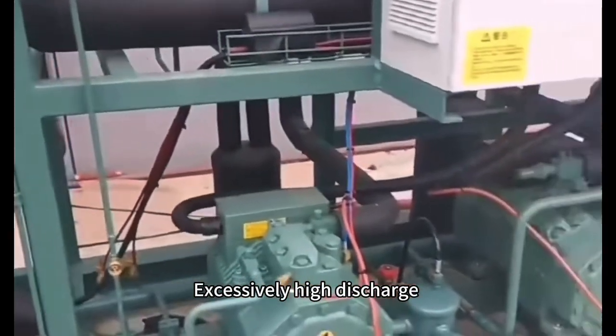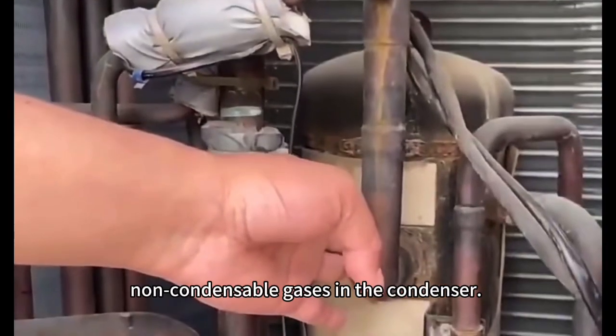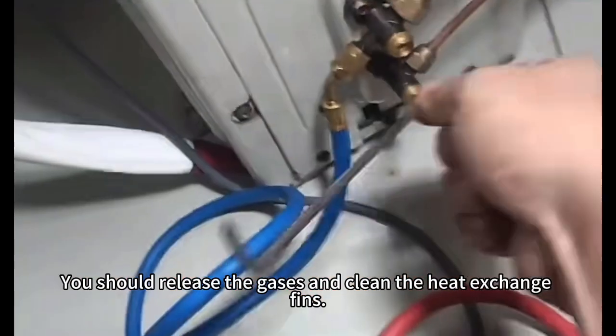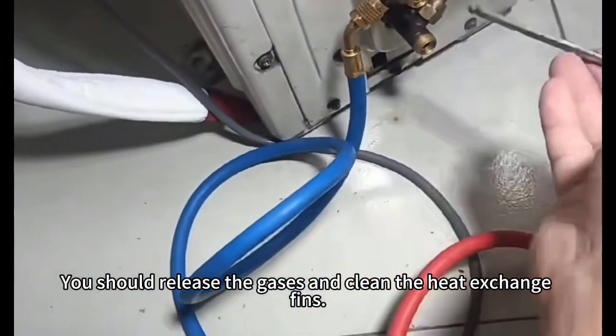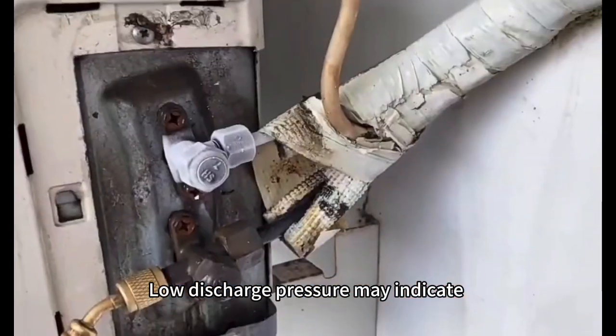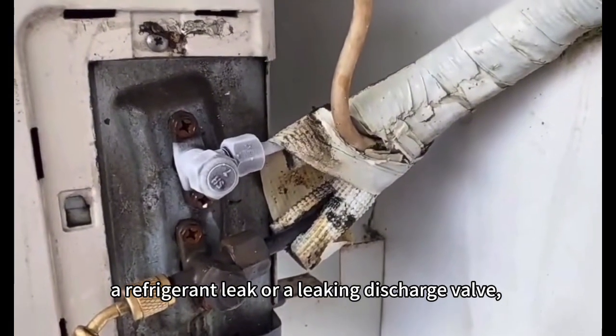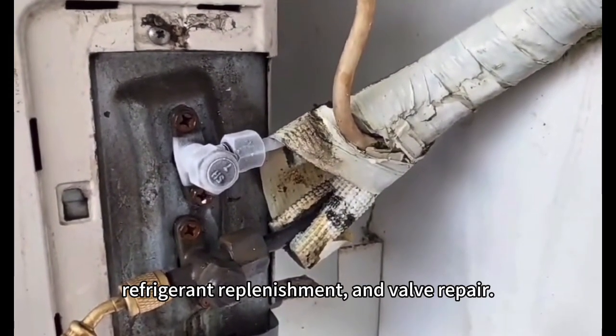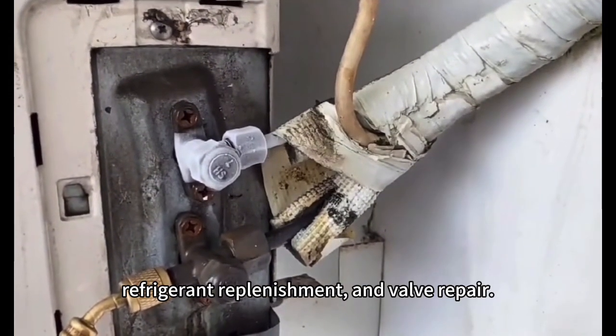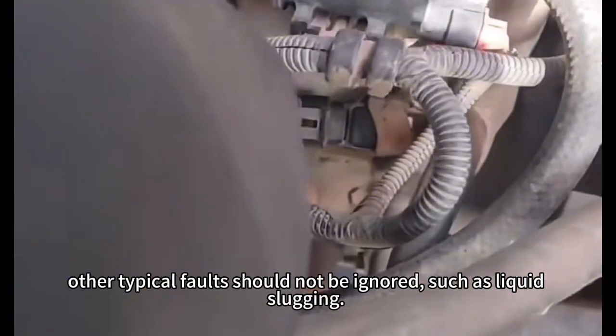Excessively high discharge pressure may indicate the presence of non-condensable gases in the condenser. You should release the gases and clean the heat exchange fins. Low discharge pressure may indicate a refrigerant leak or a leaking discharge valve, requiring leak detection, refrigerant replenishment, and valve repair. Besides these abnormal parameters, other typical faults should not be ignored, such as liquid slugging.